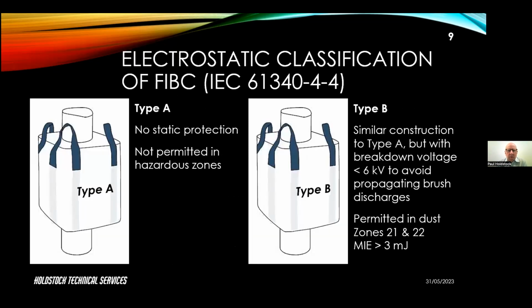So moving on to the specifics of the IEC 61340-4-4, and first of all, the classification. As I said, there's four types, the type A, B, C, and D. First of all, type A is a bag which has no static protection. So there's no anti-static additives, no conducting threads. It's basically a plain polypropylene container, and these cannot be used in any hazardous zone. So they're not permitted for use in any gas zone or anywhere where you have combustible dusts.